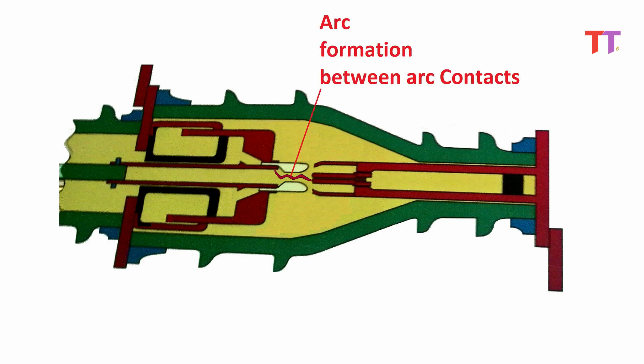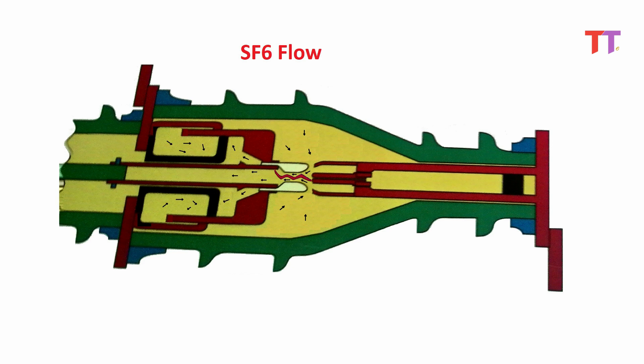Just before closing arc is formed between arcing contacts. Because distance between arc contacts is less than the distance between main contacts, arc contacts being more in length. During this operation, SF6 gas gets accumulated in the region between pistons and main contact.